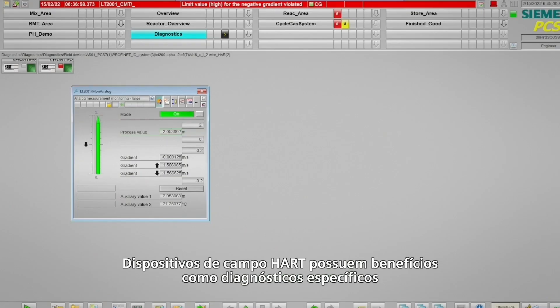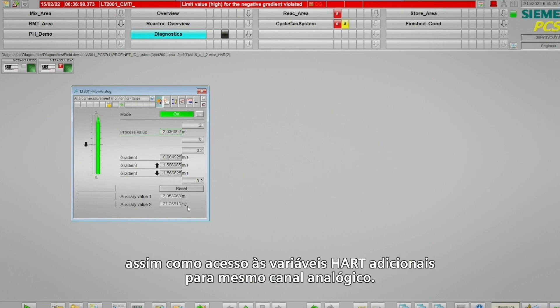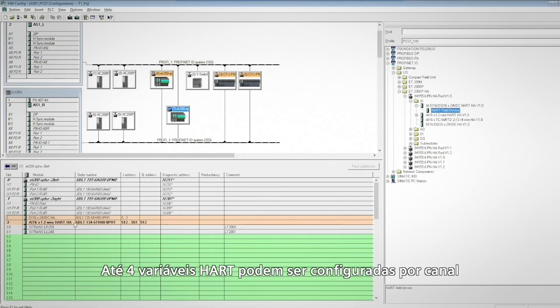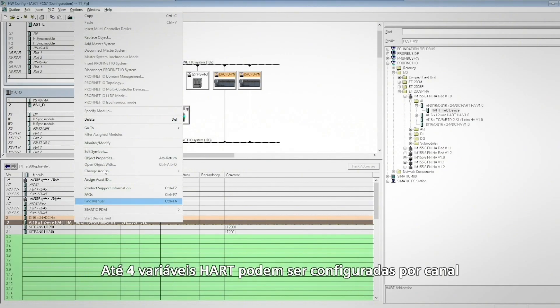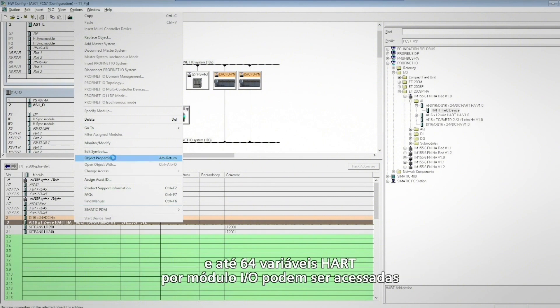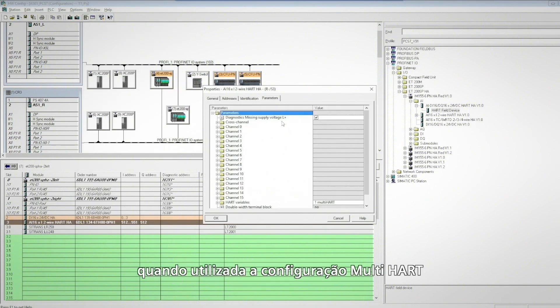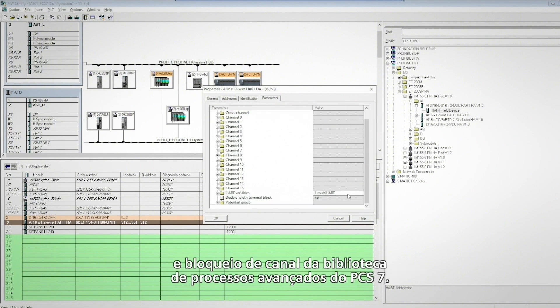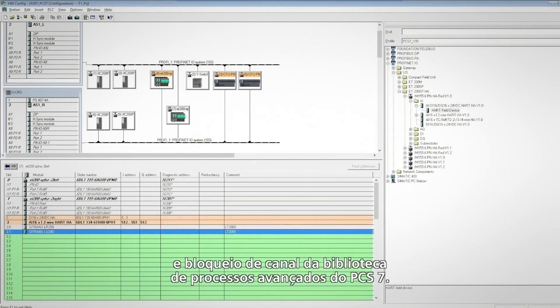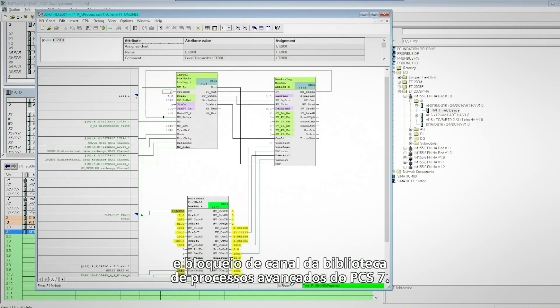HART field devices come with benefits such as device-specific diagnostics, as well as access to additional HART variables through the same analog channel. Up to four HART variables can be configured per channel, and up to 64 HART variables per I.O. module can be accessed when using the multi-HART configuration and channel block from the PCS7 Advanced Process Library.